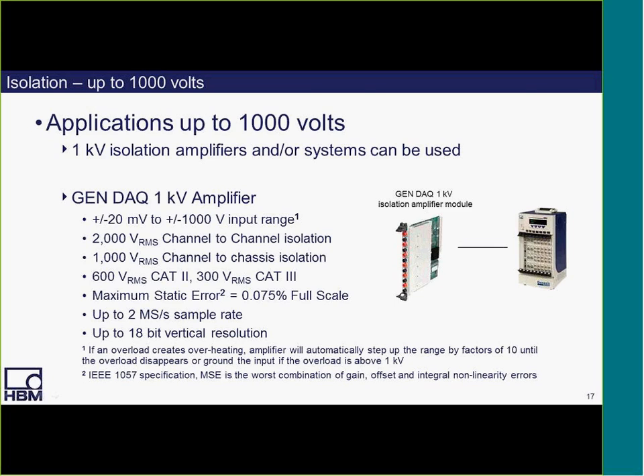Looking below on the slide, I've noted that if an overload creates overheating, the amplifier is automatically going to step up the range by factors of 10 until the overload disappears, or even ground the input if the overload is above 1,000 volts. So a nice and unique safety measure for the equipment in case you do happen to inject, let's say, 1,000 volts when it's on the 20 millivolt range. You're not going to damage the amplifier because it provides automatic protection.